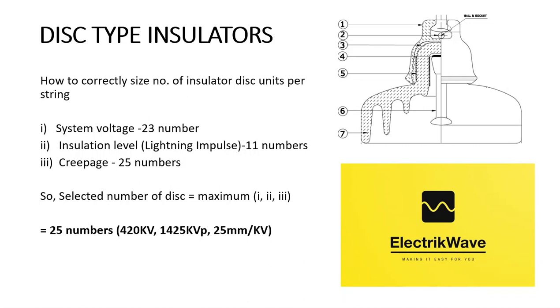As we have now calculated disk units per string: for system voltage it is 23, for insulation level (lightning impulse) it is 11, and for creepage it is 25. The selected number of disks will be the maximum of these three, which is 25 numbers.